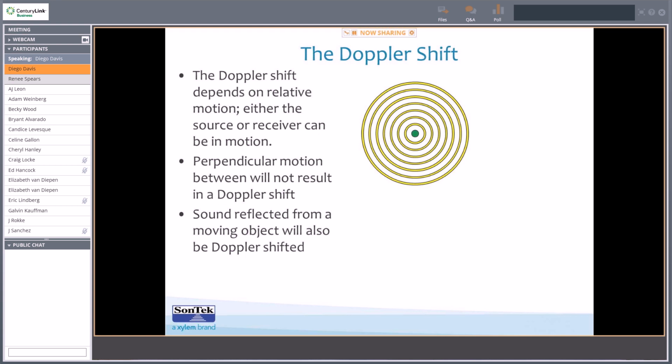Now, I imagine you all can imagine that the more particulate we have in the water, the better scattering conditions we're going to have, the higher number of objects we're going to be able to measure, and the better and more accurate our velocity measurement. So one really key part of this is that water with very low scatter, so this is water that's very, very clear, typically fresh spring water, any sort of treated water before it receives any sort of minerals or additives, is going to be water that's very difficult to measure because there are very few objects in it that we can use to measure the water velocity.